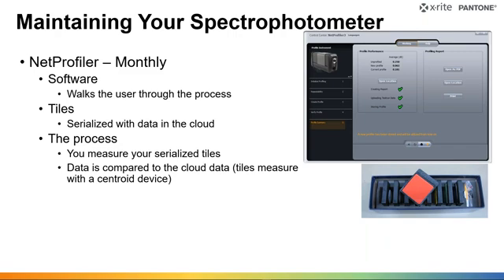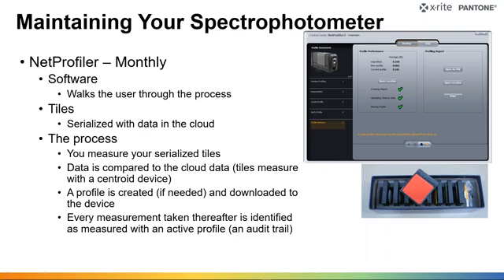Now you measure with yours, and we get a calculated value. You can see up here, this one says unprofiled, it was 0.250 delta E. So that's how far off that instrument was compared to the centroid measurement on those tiles. But you'll see underneath there, it says new profile generated 0.06, okay? And so a profile is created if it's necessary, if it's needed, and downloaded into the device. So that profile is going to adjust for how that instrument measured differently across all of these different colored tiles. There's whites and grays and some chromatic tiles and so forth. And then that profile, once loaded into the instrument, every measurement taken thereafter is identified as measured with this active profile. And so it's like every month bringing your device back to the centroid, getting it as close to the centroid as we can. And that work that's done every 30 days, you profile again.